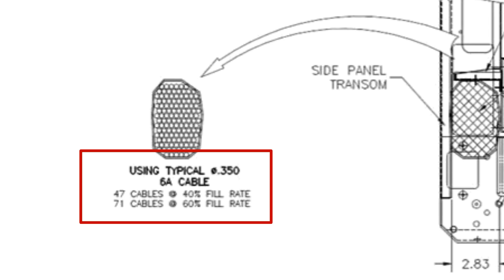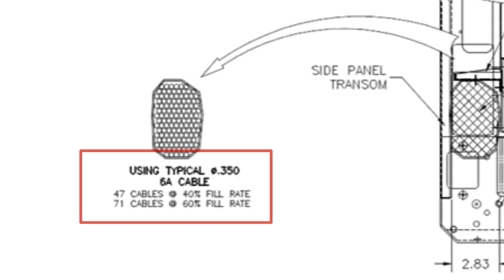And if we're willing to go to 60% fill and spend some time grooming the cables for a tighter fit, we're told that we should be able to get 71 cables in there.